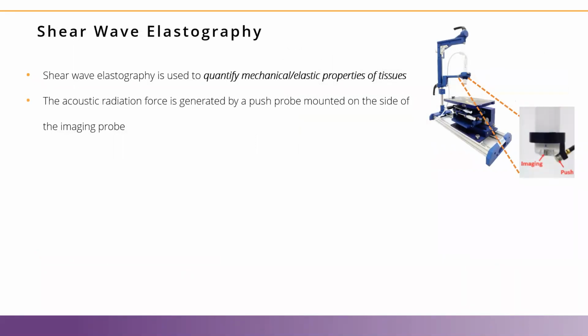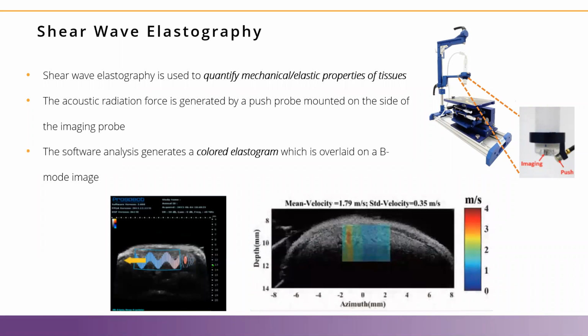An additional advanced technique is called shear wave elastography. When we're doing elastography, we're looking at the changes in the mechanical or elastic properties of a specific tissue. How this works is that there's an additional probe mounted onto the side of the imaging probe, called the push probe. It sends in a push pulse, an ultrasound pulse, and then detects how fast that pulse propagates throughout the tissue. As the sound propagates through the tissue, if it's healthy and normal, it's going to have a very specific speed. If there's a lesion or a change in how that tissue allows the sound wave to propagate through, then we're going to see a change in how fast the sound wave propagates. We can see that in a colored elastogram, which is overlaid on top of the B-mode image. Here we see the scale, blue, green, yellow, red, which shows us the change in speed of that propagation of the push pulse.